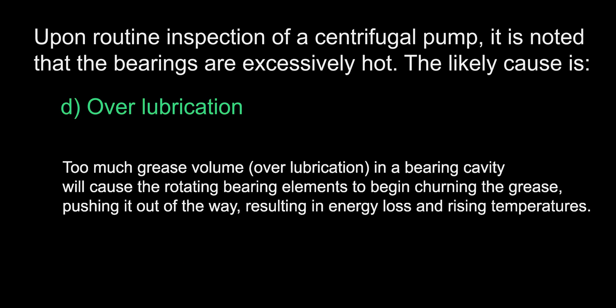The answer is D, over lubrication. Over lubrication can lead to high operating temperatures, higher costs due to wasted grease, collapsed seals, and in the case of greased electric motors, energy loss and failures. The best way to avoid these problems is to establish a maintenance program and follow the operating and maintenance manual of the motor or instrument.